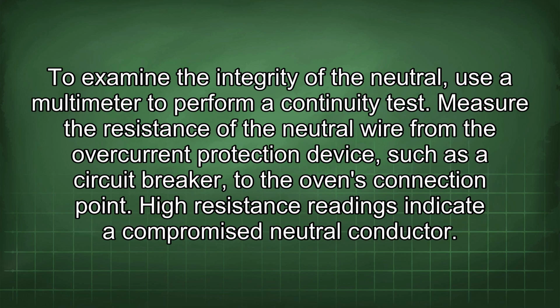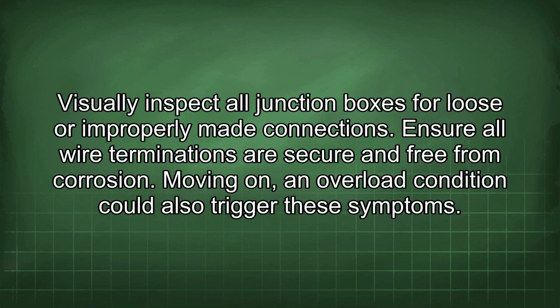To examine the integrity of the neutral, use a multimeter to perform a continuity test. Measure the resistance of the neutral wire from the overcurrent protection device, such as a circuit breaker, to the oven's connection point. High resistance readings indicate a compromised neutral conductor. Visually inspect all junction boxes for loose or improperly made connections. Ensure all wire terminations are secure and free from corrosion.